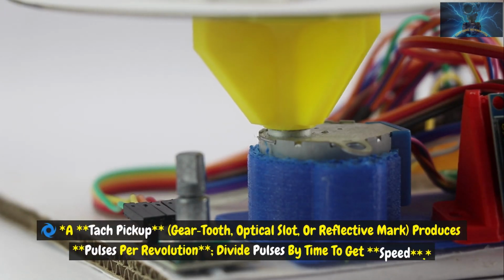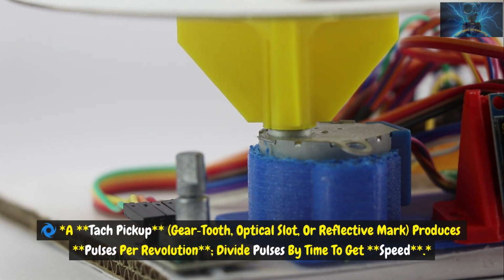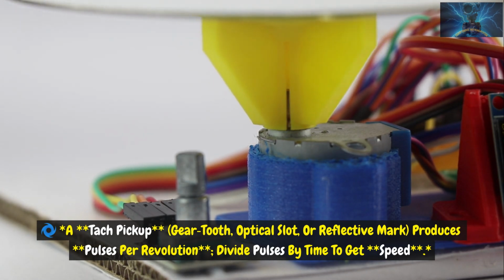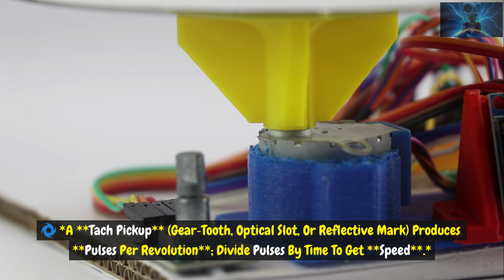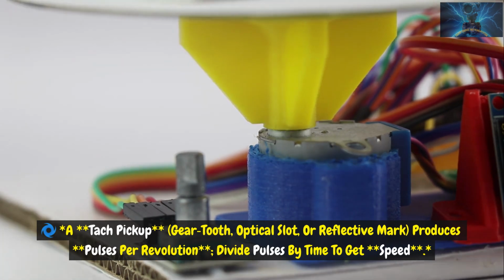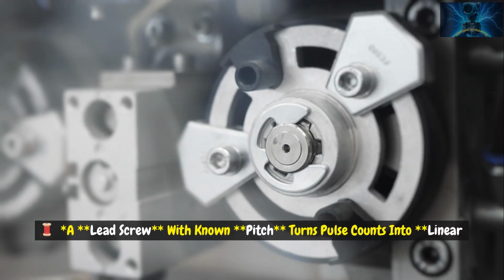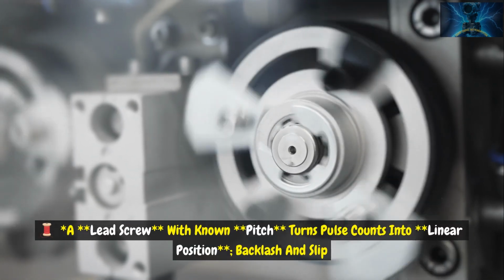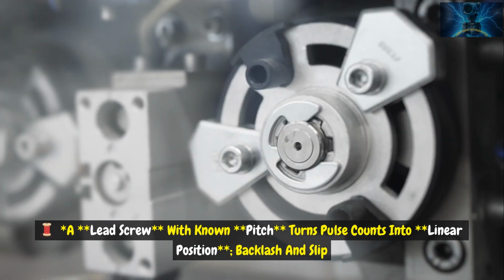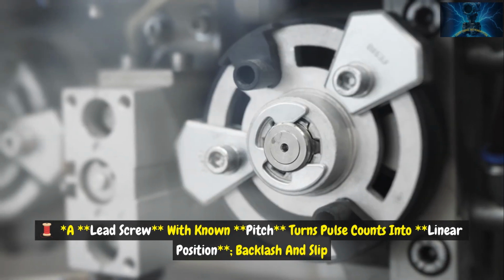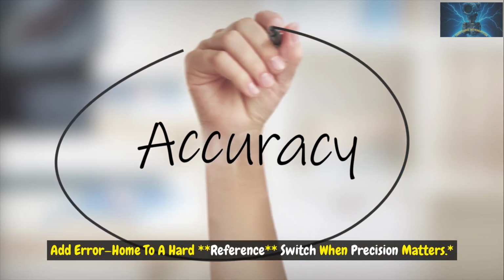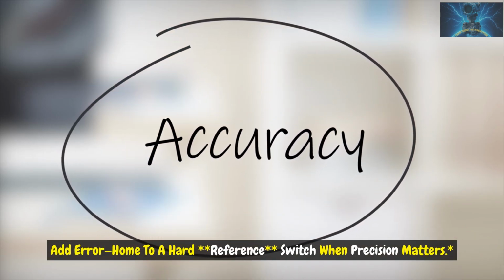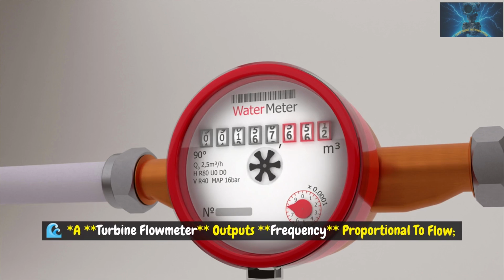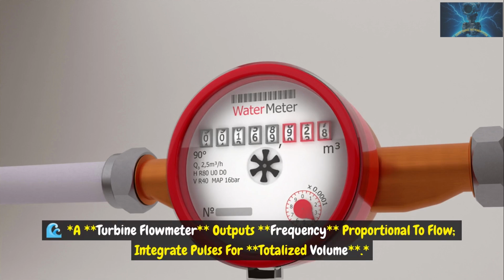Indirect sensing: inference you already use. A tach pickup, such as a gear tooth, optical slot, or reflective mark, produces pulses per revolution. Divide pulses by time to get speed. A lead screw with known pitch turns pulse counts into linear position. Backlash and slip add error, so home to a hard reference switch when precision matters. A turbine flowmeter outputs a frequency proportional to flow; integrate pulses for totalized volume.